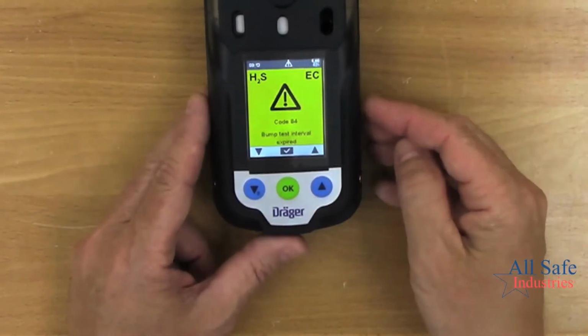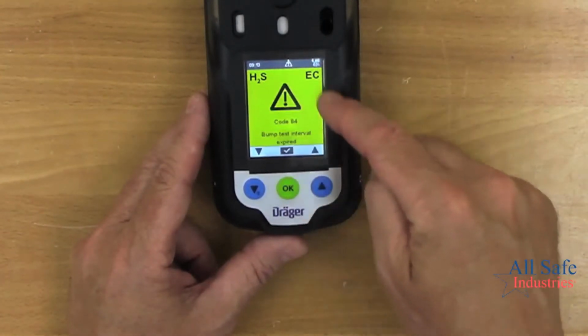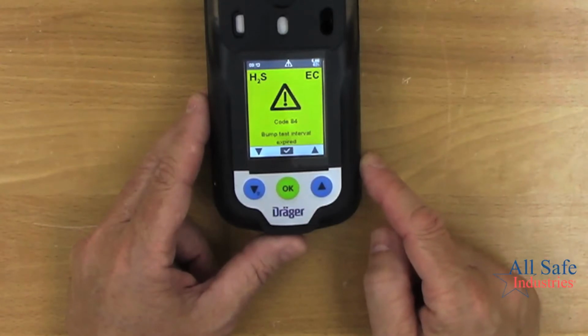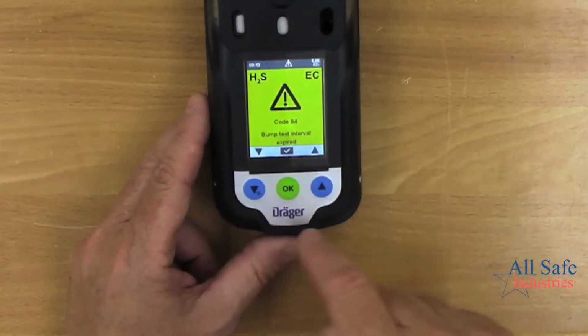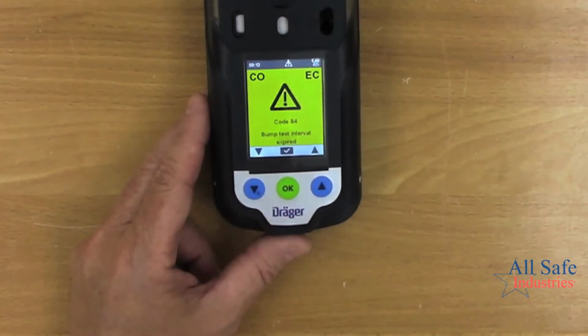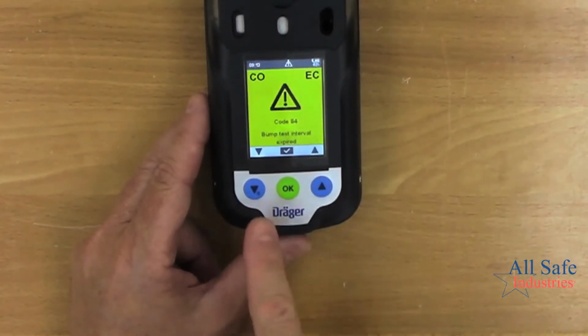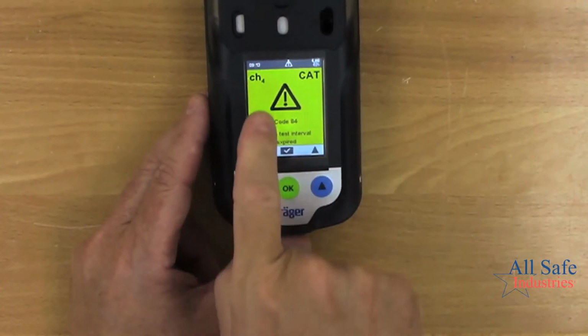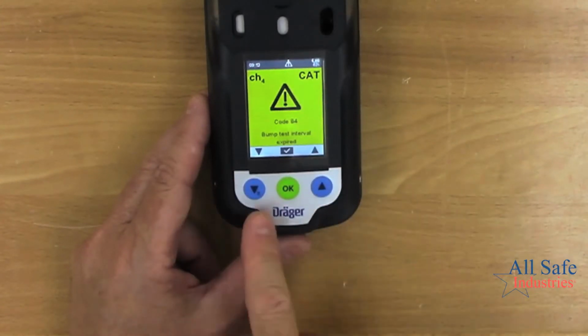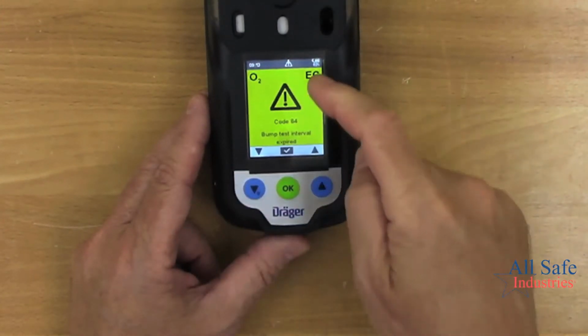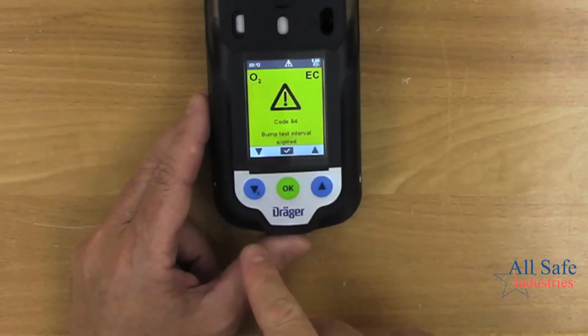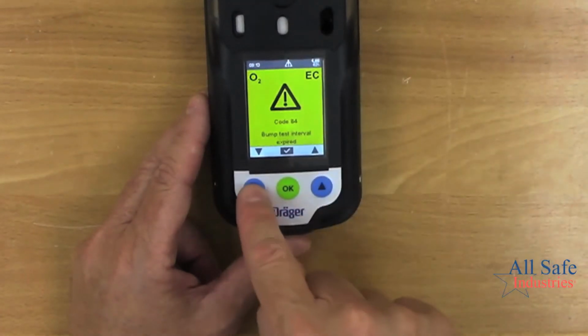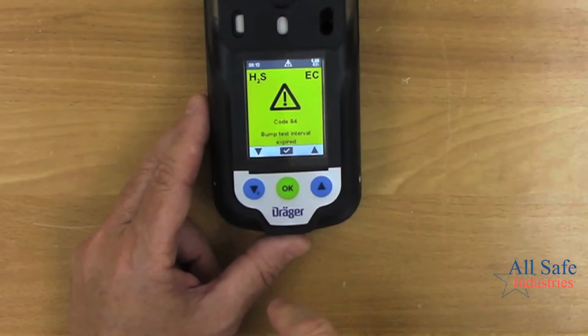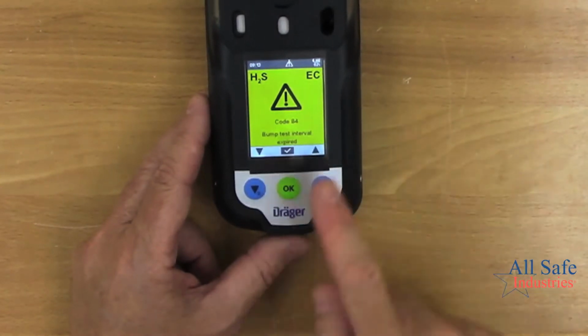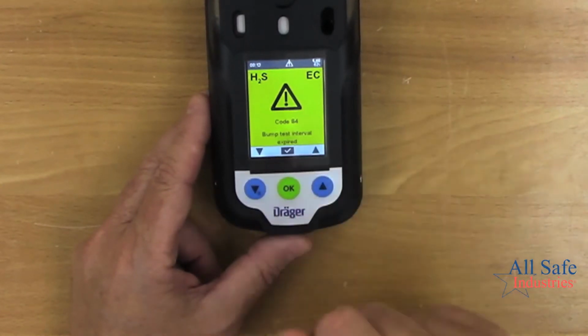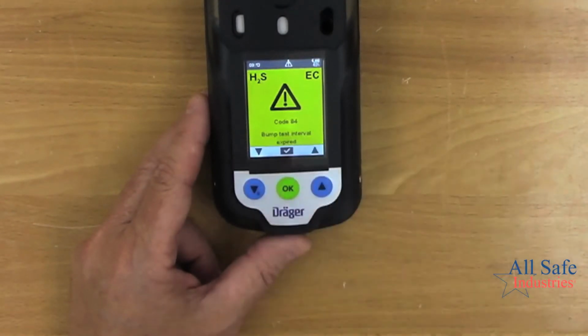This came out of our inventory, and it's telling me that I haven't been bump tested in a while. I can use the up and down buttons to toggle through and see more messages. My CO sensor hasn't been bump tested, my methane catalytic bead sensor hasn't been bump tested, and my oxygen sensor hasn't been bump tested. It's nice that it gives an explanation of each of those warnings or alarms.